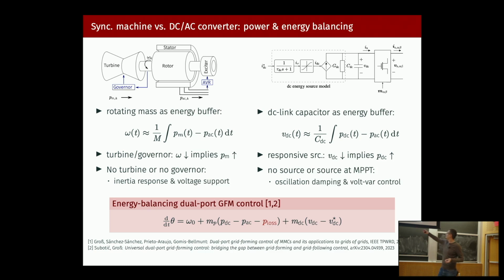How does this work today? If you have a load step in your system, you take the power to supply this out of the kinetic energy in the machine. That reduces your frequency. Then the turbine governor system picks up on this, burns more fuel, creates more steam to up the power generation. So the frequency of the machine, in essence, is really just an indicator of power imbalance or energy unbalance in that system.